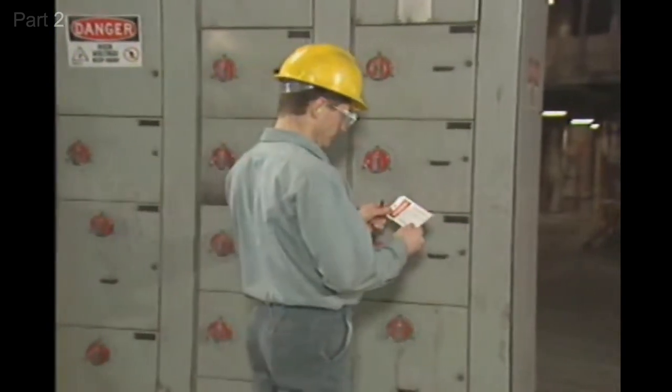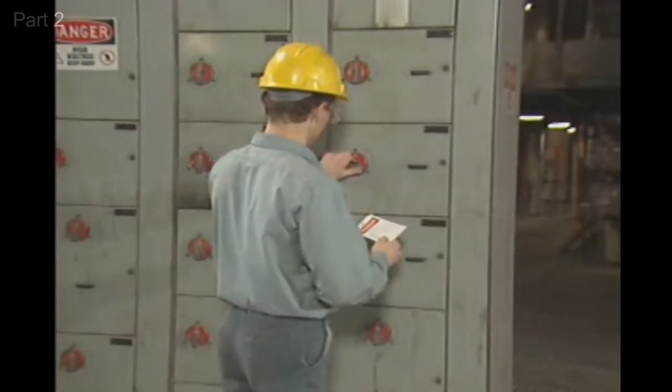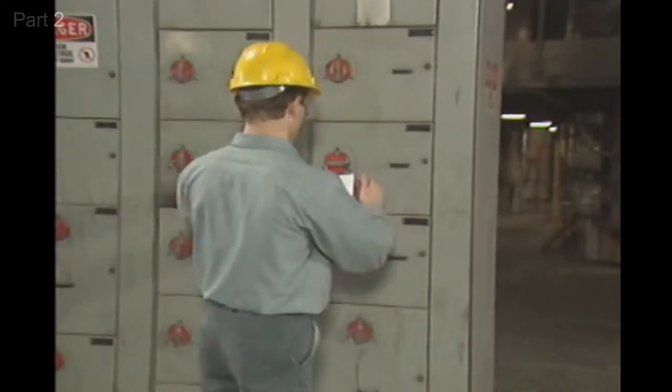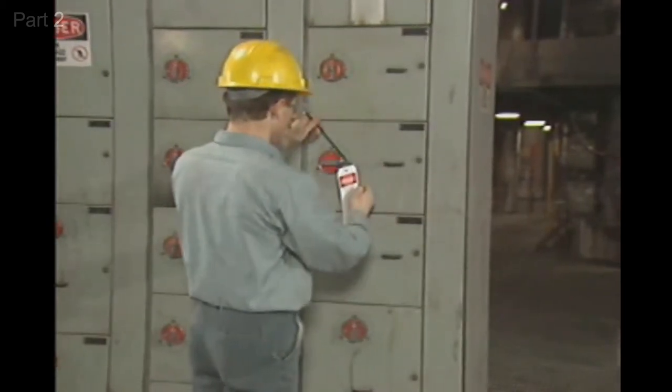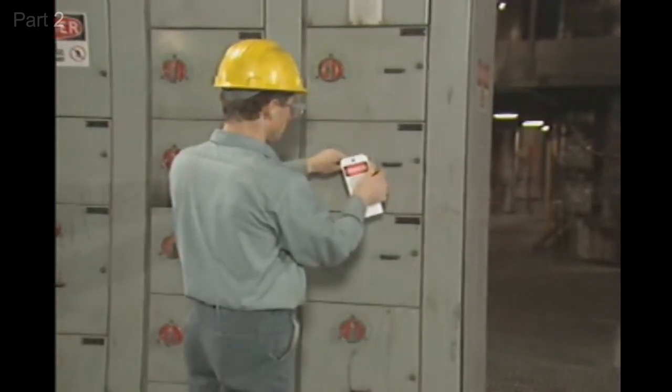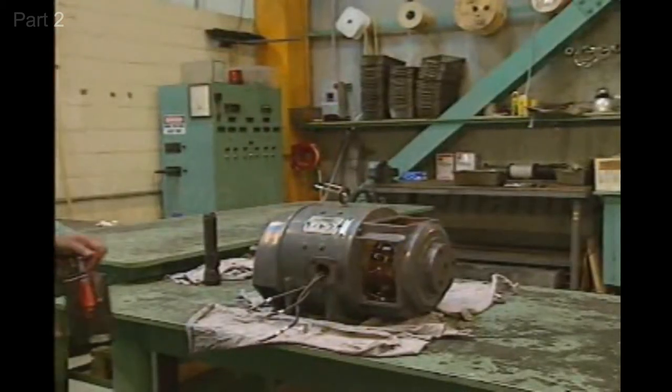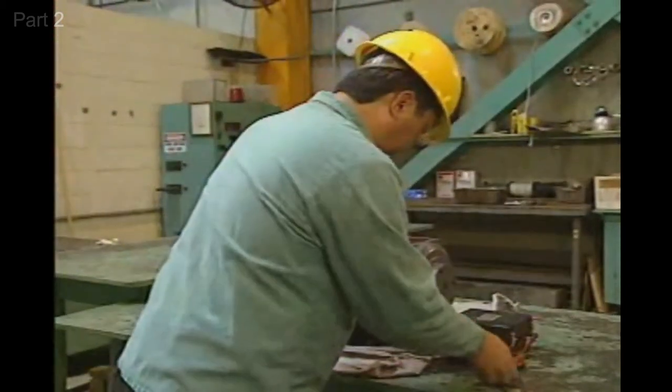The motor to be checked should be de-energized, locked out, and tagged according to approved procedures. Troubleshooting a de-energized motor helps prevent personal injury and protects the motor and the test equipment from damage. The motor in this example has been taken to a shop for troubleshooting.